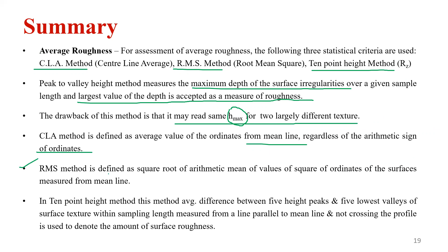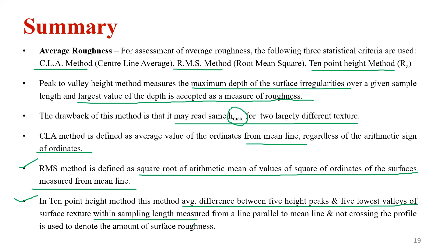But in the center line average method, it is defined as the average value of the ordinates from the mean line, regardless of the arithmetic sign of the ordinates. So here we neglect the sign of the ordinate values, and only consider the magnitude. The second method, the root mean square method, is defined as the square root of the arithmetic mean of the values of the square of the ordinates of the surface measured from the mean line. And in the 10-point height method, the average difference between the 5 highest peaks and 5 lowest valleys is considered within the sampling length.